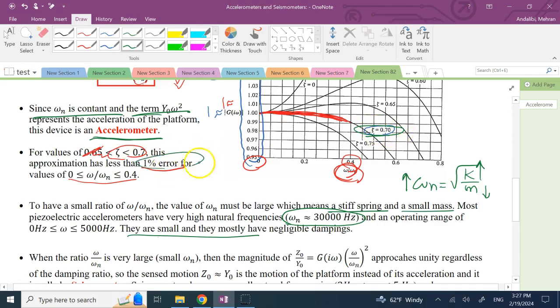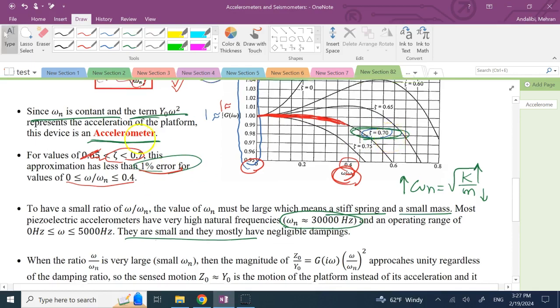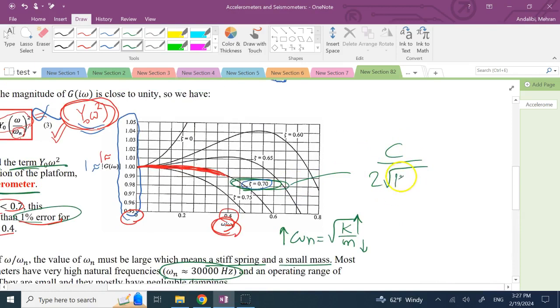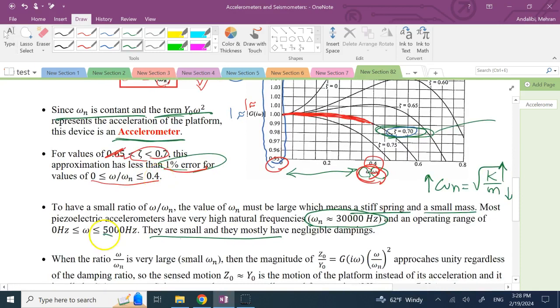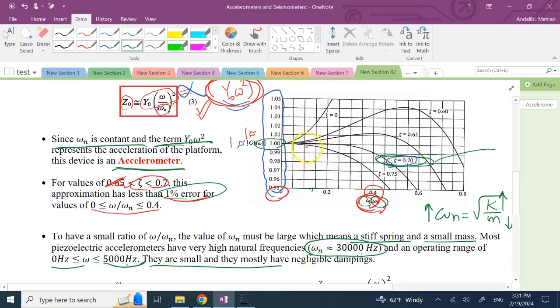Choosing ζ so that ζ = c/(2√(km)) ≈ 0.7 gives a good frequency range. If ωₙ = 30,000 Hz and the usable ratio is up to 0.4, that's 12,000 Hz. In practice, manufacturers limit the operating range to about 5,000 Hz — a ratio of roughly 1/6 — ensuring |G(jω)| is very close to 1 for excellent accuracy.